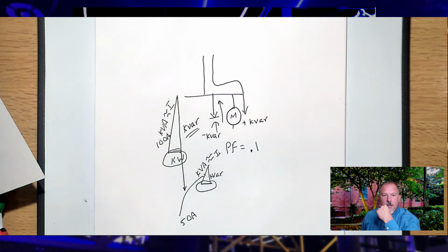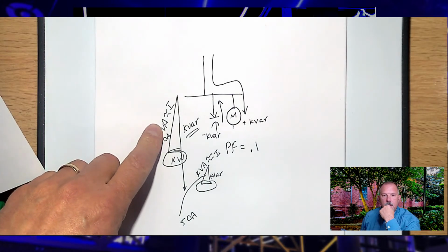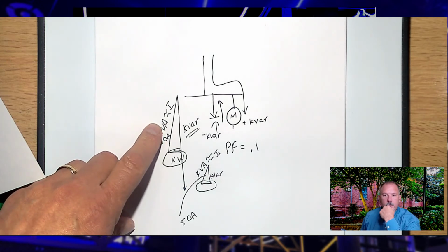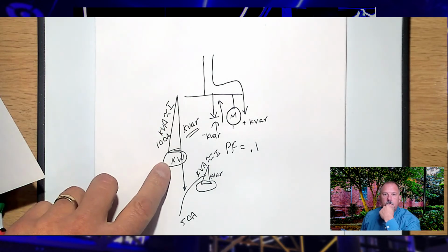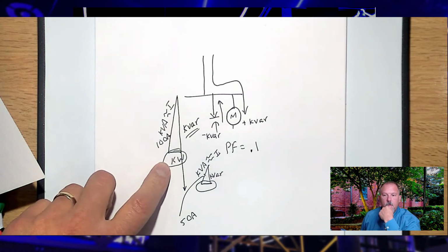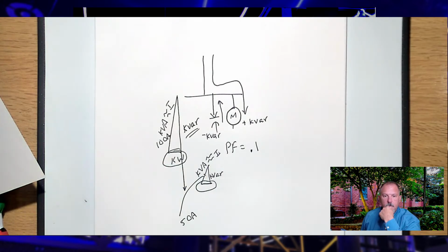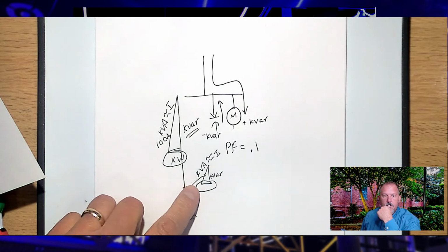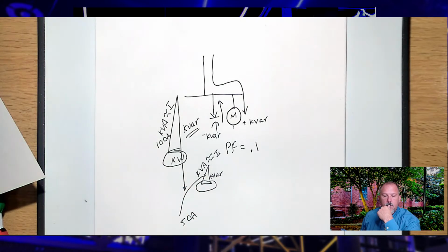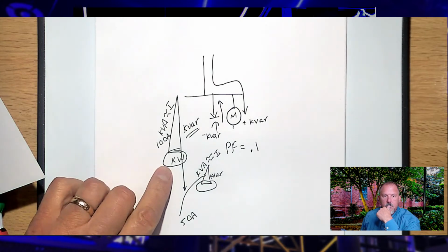And that's where they fool people, because guess what? Do we pay for kVA? No, especially not in our house. We pay for watts or kilowatts, and we pay for kilowatt hours. In a commercial building or even an industrial plant, most of the time we pay for kilowatt hours and we also pay for kilowatt demand. So in that case, we pay for kilowatts in both cases. There are special exceptions where the utility will bill you a power factor penalty, but that's saving money, and we can come back to that. That's not saving power as we define it, as kilowatts.